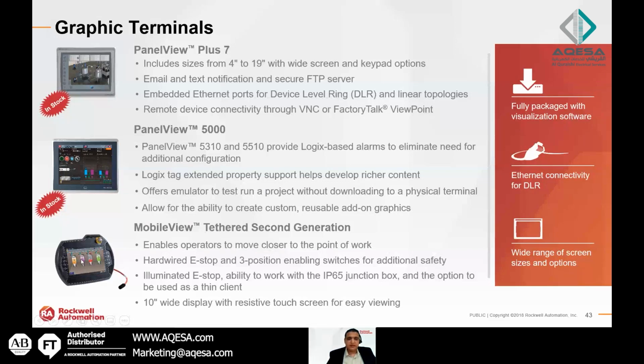The PanelView Plus 7 works with FactoryTalk View Machine Edition. It comes from 4-inch up to 19-inch with widescreen 16:9 aspect ratio. It supports an FTP server, embedded Ethernet port with DLR, remote connectivity over VNC and FactoryTalk Viewpoint, and has an embedded server for Viewpoint, our web server. So if you are anywhere on your site, you can enter the IP of the HMI and use the Viewpoint client to remotely monitor and interact with the PanelView, with a security access level.